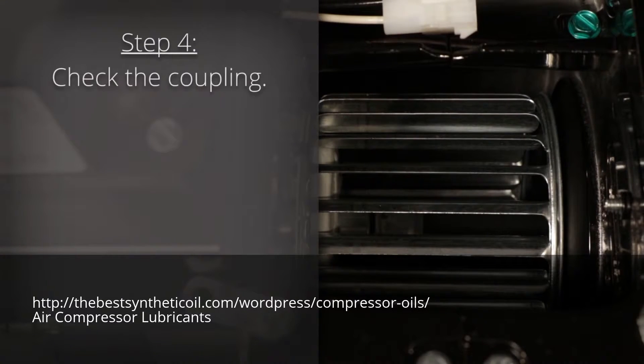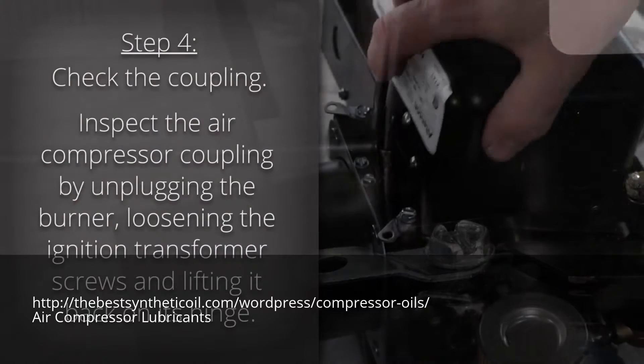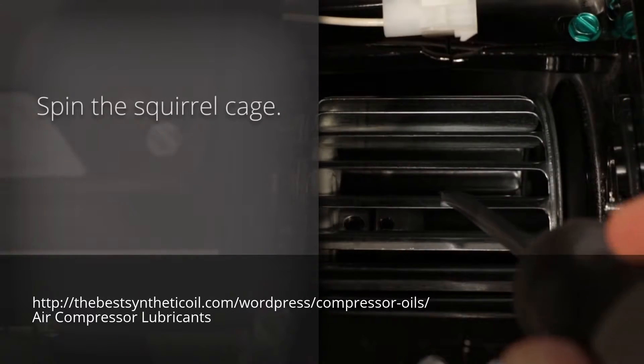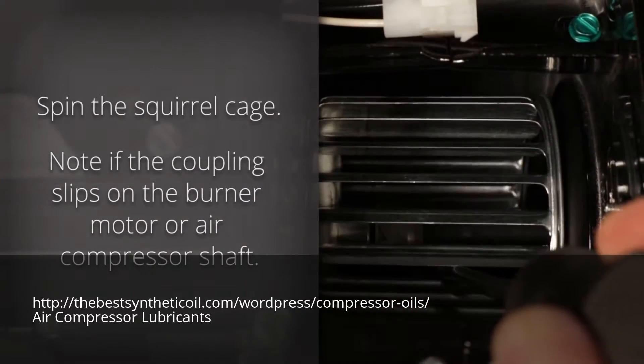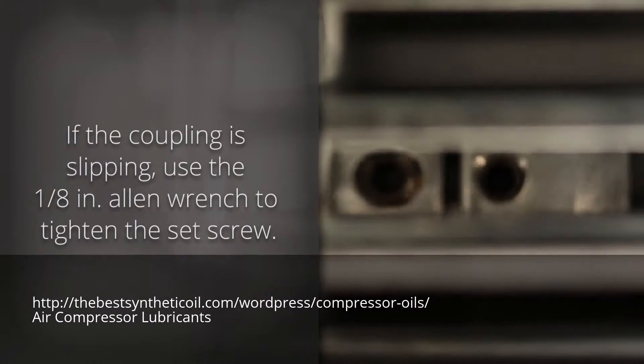Step 4: Check the coupling. Inspect the air compressor coupling by unplugging the burner, loosening the ignition transformer screws and lifting it back on its hinge. Then spin the squirrel cage and note if the coupling slips on the burner motor or air compressor shaft. If the coupling is slipping, use your 1/8 in. Allen wrench to tighten the set screw.